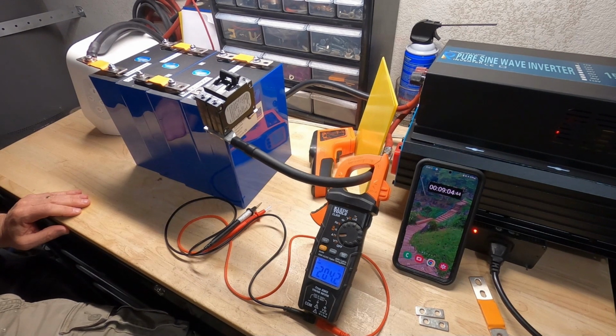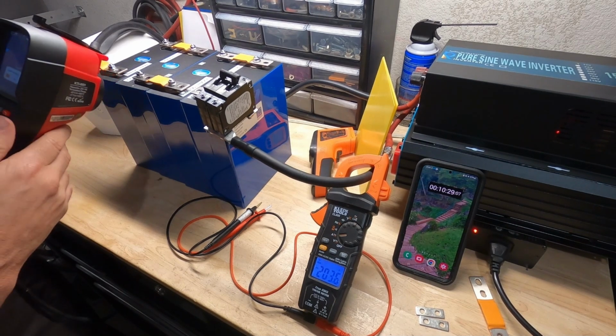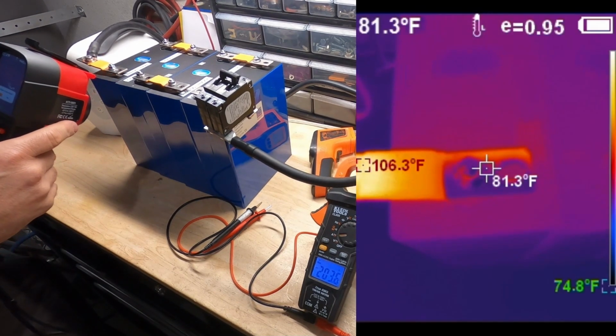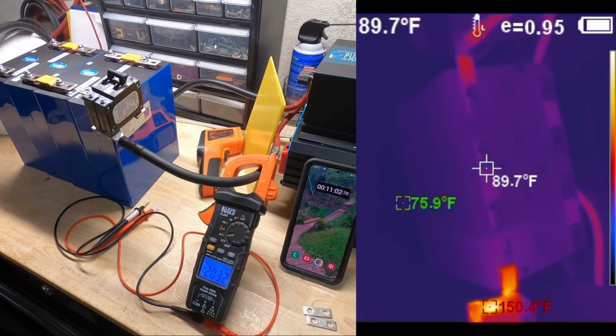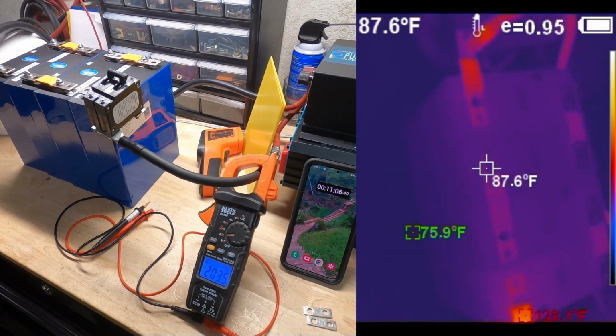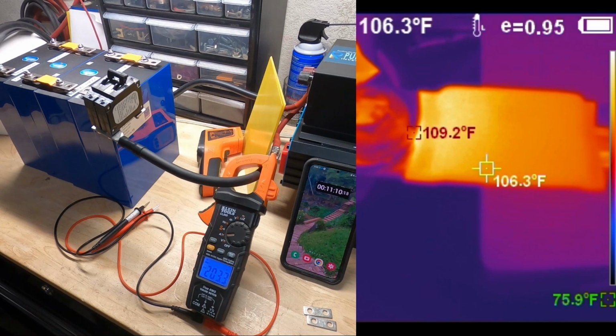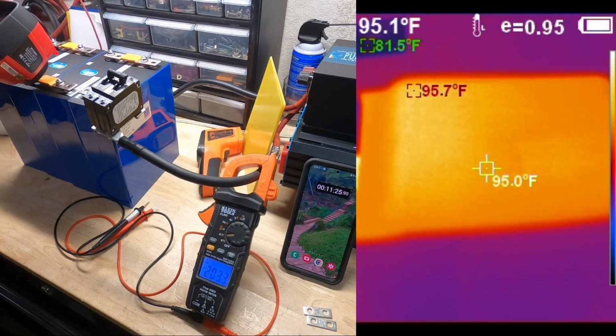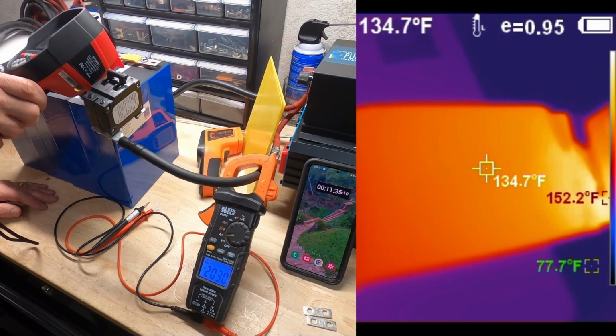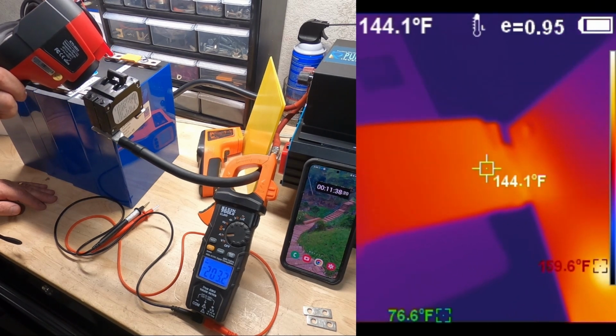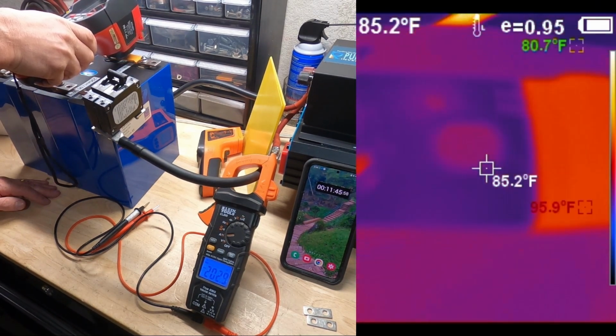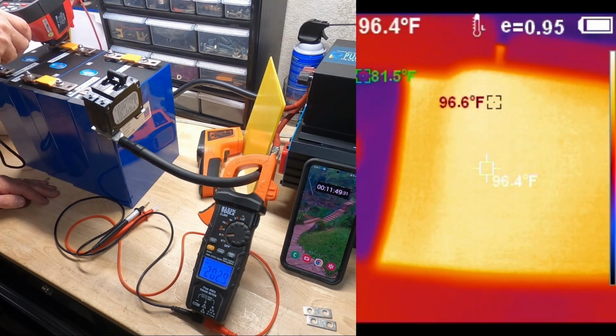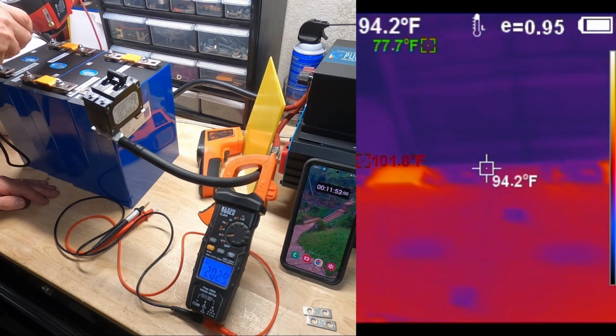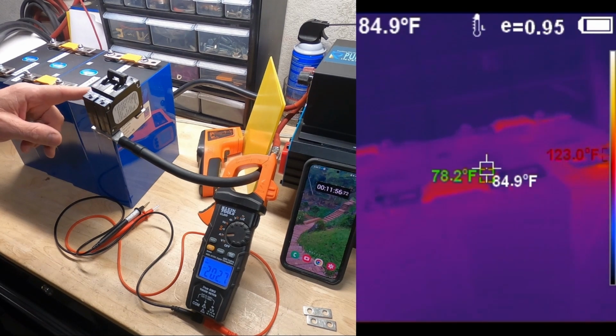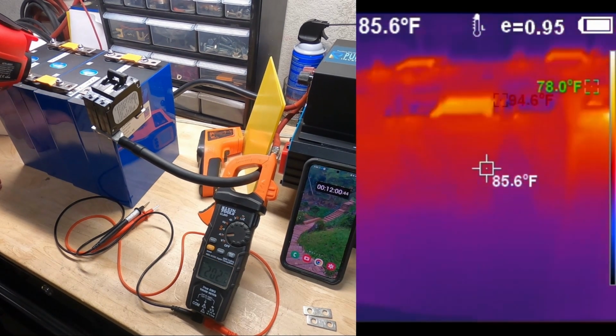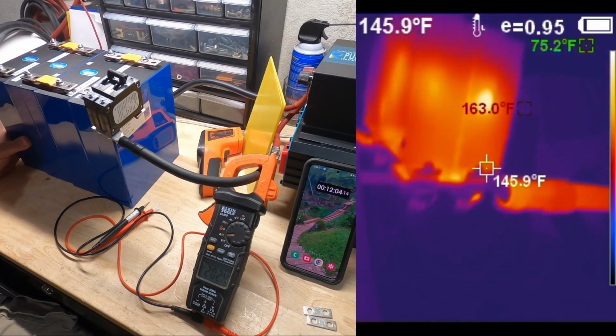Coming up on 10 minutes. Okay, we're gonna do our 10-minute check here. It's 10 minutes, 30 seconds so far. So looking at the entire pack, the bus bar on the breaker is still the hottest. Let's look at the individual bus bars. 100 degrees on that one. Okay, we're at 140 on that one. That's the one that's connecting the breaker. 100 degrees on that one. And 100 degrees on this one. They're all consistent. Every bus bar in the pack, save for this one because of the breaker, is at 100 degrees or less. That is nuts. What is going on here?